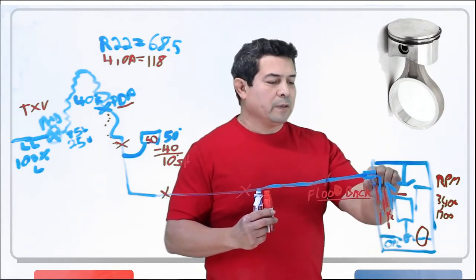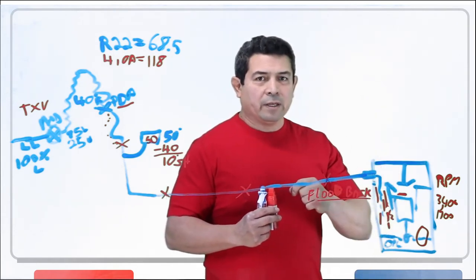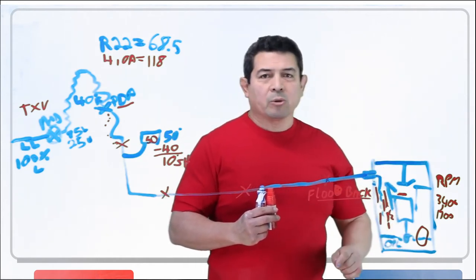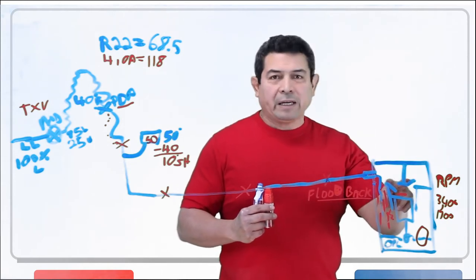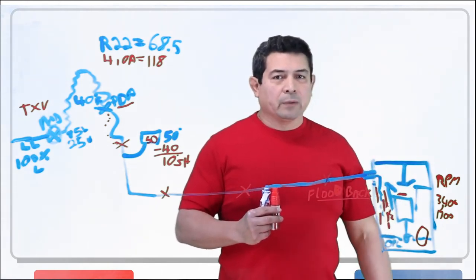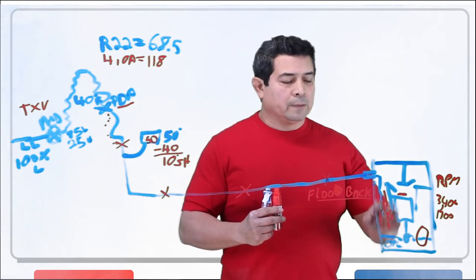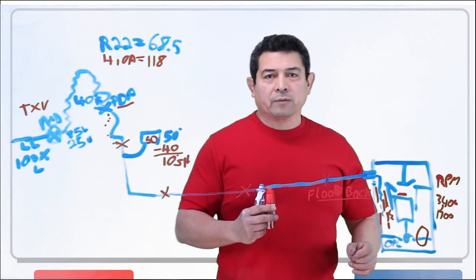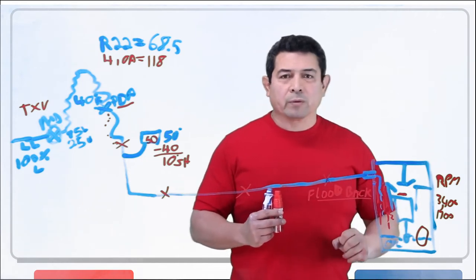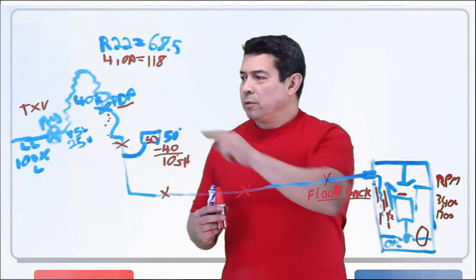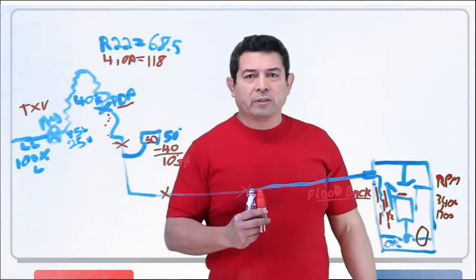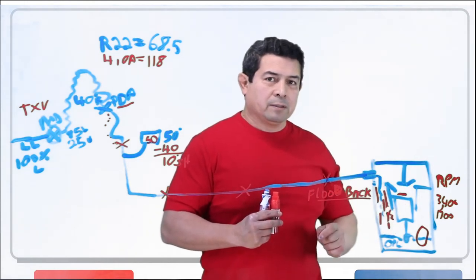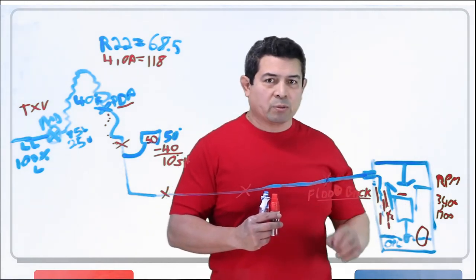That piston comes up. Something is going to break. Either the piston is going to go in there sideways, because I have seen that. The piston goes in there sideways or maybe the connecting rod here breaks. Sometimes the valves, suction discharge valves, break because of the liquid. Now, once that happens, then there's nothing we can do. We have to change the compressor. We put a new compressor in. What happens when we put the new compressor in and we don't adjust or replace the metering device? That means that the same problem is going to happen again. Same problem. We're going to lose this compressor.